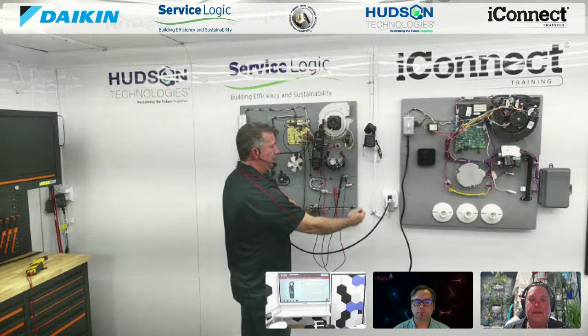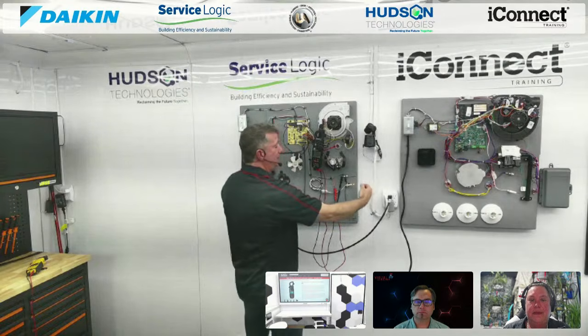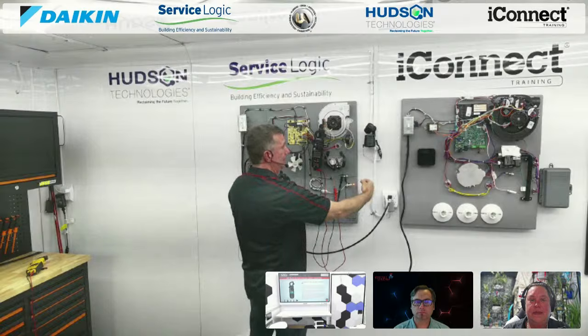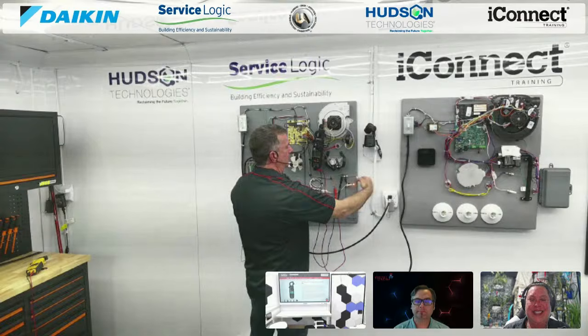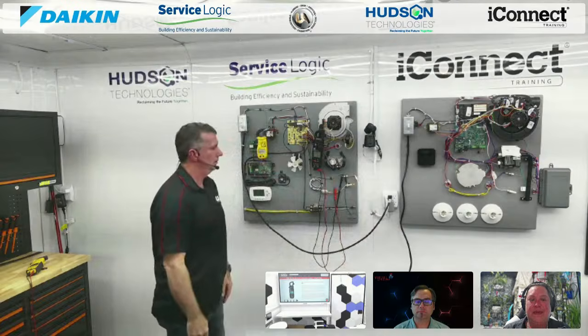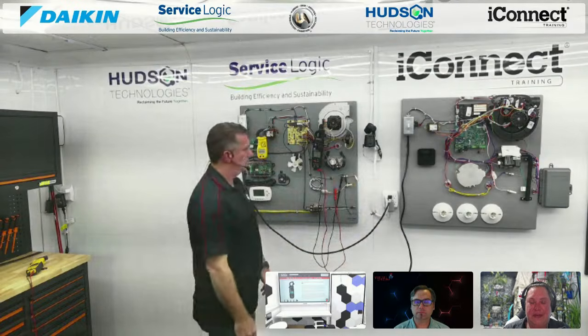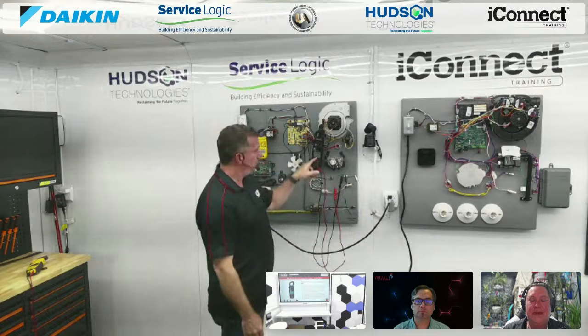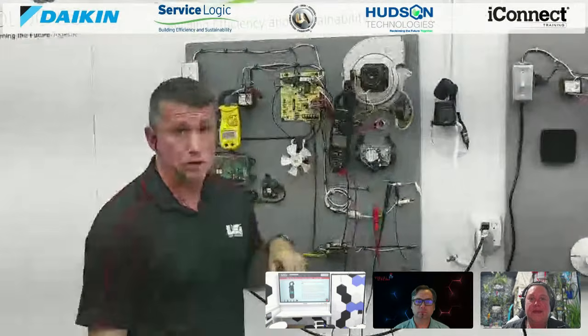All right, so the next click's hot surface igniter. The next one will be our gas valve. All right, I can't read flame yet. I have to wait till my gas valve opens. And after my gas valve opens, introduce my load. So I am right now producing a load of 3.1 microamps that is going between this 43 volts AC and ground. So that's what we're reading with our microamp setting.